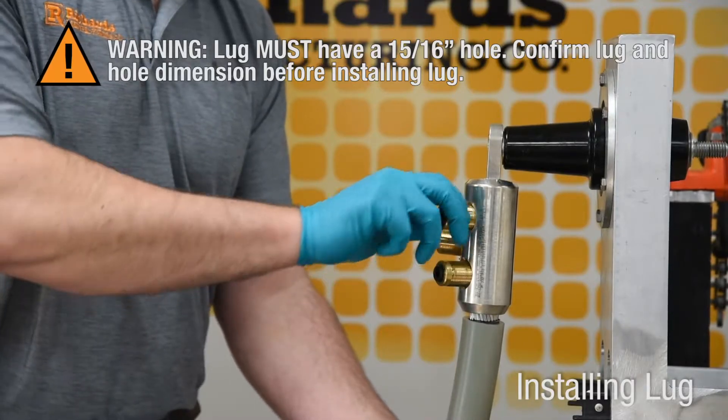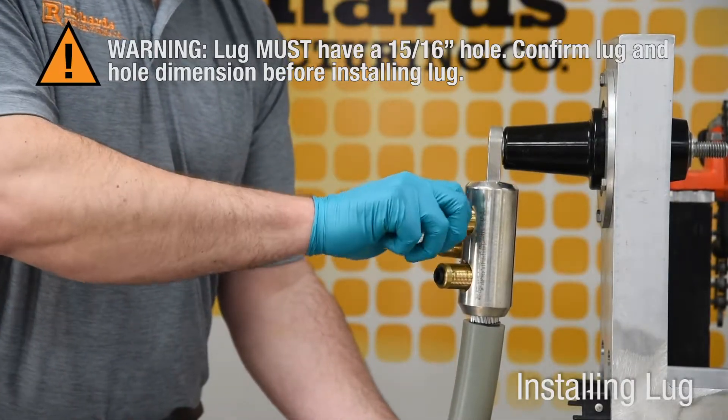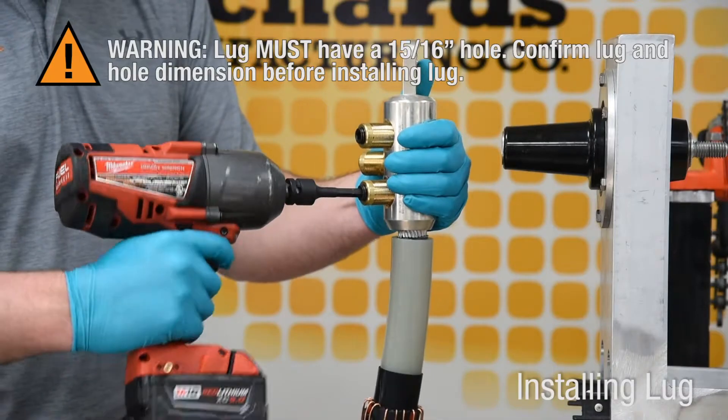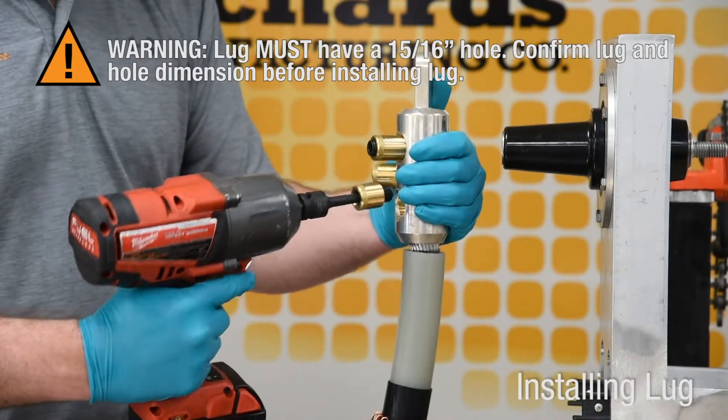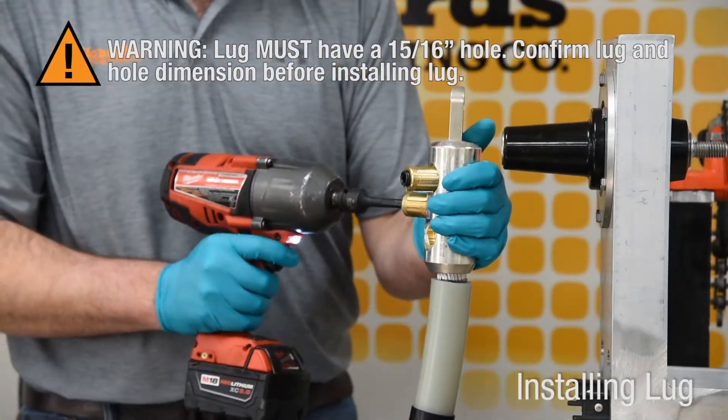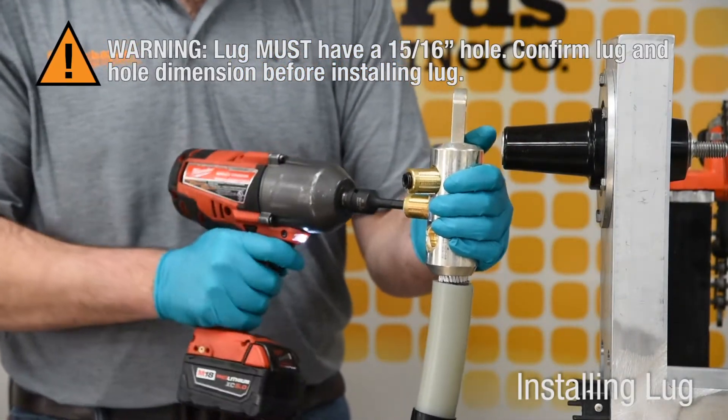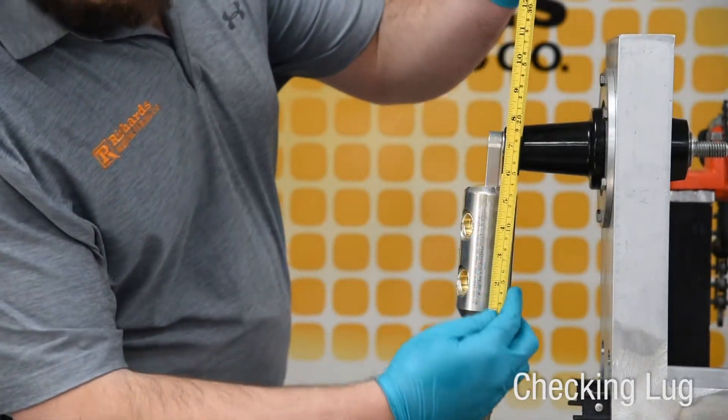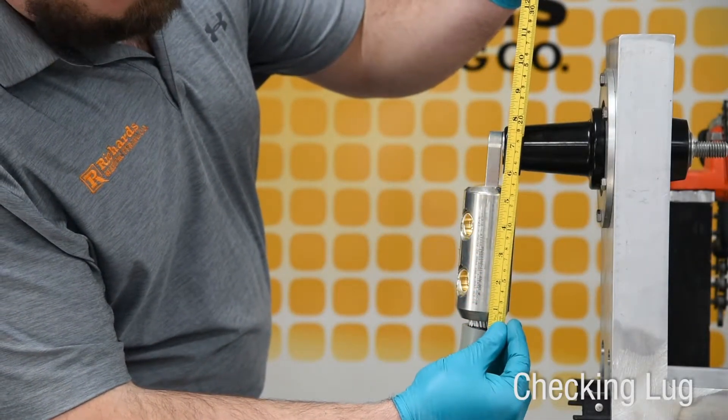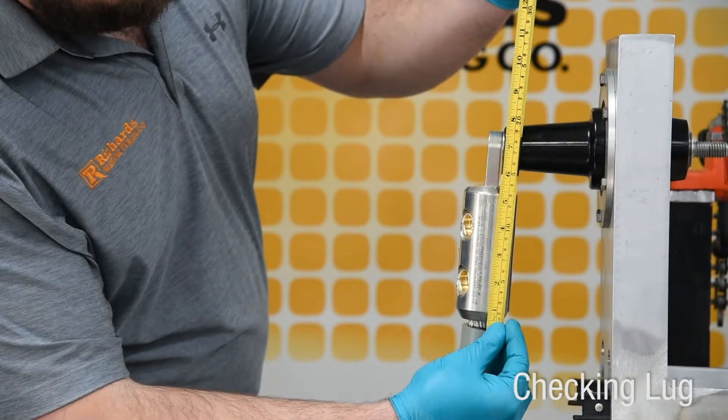Install either a compression or shear bolt lug with 15 sixteenths inch threaded hole according to manufacturer's instructions. Lug must have a 15 sixteenths inch hole. Confirm lug and hole dimension before installing lug. Confirm distance from top surface of lug to insulation cutback does not exceed 7 and 1 quarter inches.